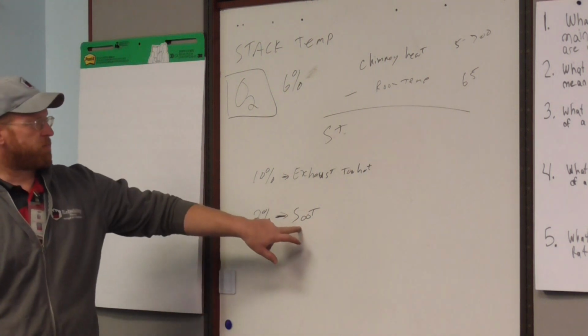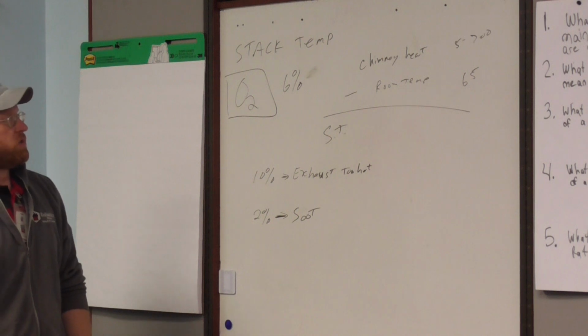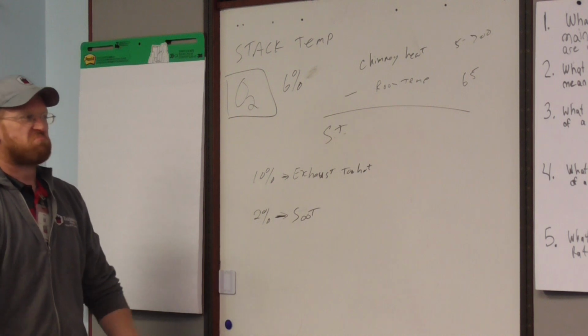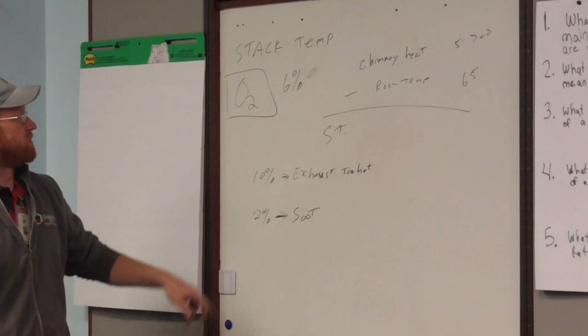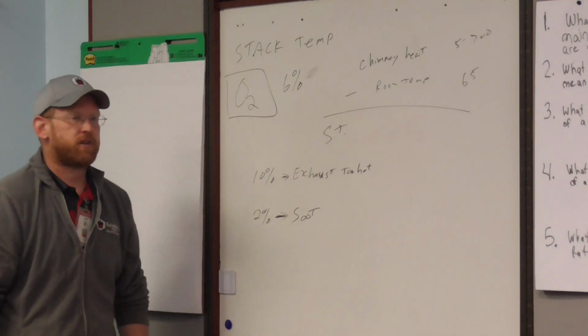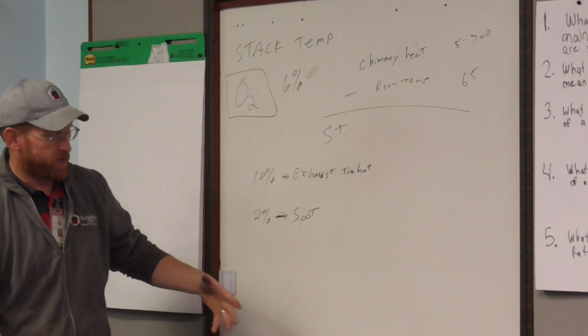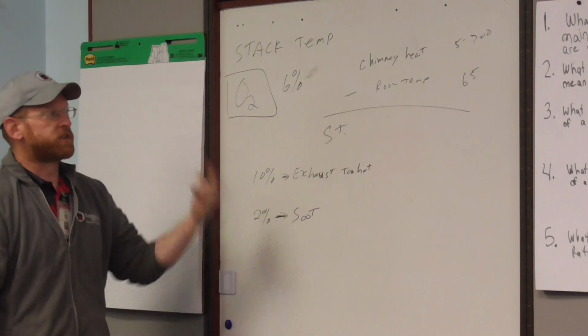There is another byproduct of soot. It is a great insulator. Yeah. Soot ash is one of the best insulators you can have. So if somebody's been running this thing and coated the inside of it with soot, yours is also gonna get too hot. Because if your heat exchanger is insulated, it can't exchange heat. So all of it's gonna go right up the chimney.